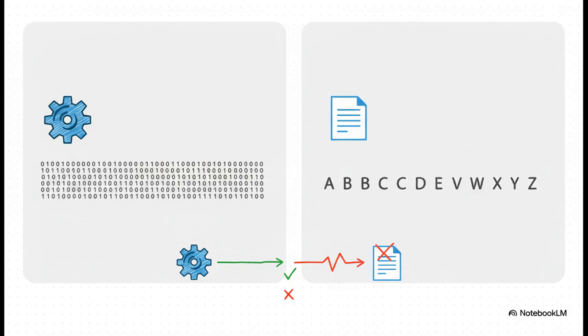It's pure machine talk. The other one is ASCII mode. This one's less efficient because it sends every byte as two human-readable characters, but that can sometimes make it easier for a person to look at and troubleshoot. But here's the most important thing: every single device on the network has to be speaking the same dialect, no exceptions.